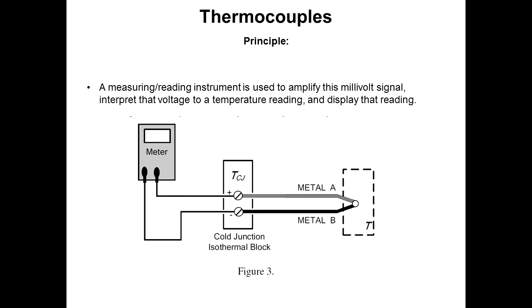So we have a measuring instrument here that amplifies this millivolt signal. The signal is very weak, so it needs to be amplified to be read by a meter. So I have a cold junction and a hot junction going to the meter. There's a thermistor on the cold junction measuring the temperature, and that gives me my ambient temperature, which is added back, or referenced to 0°C, and the difference is added back to the signal coming from the hot end of the thermocouple, and that's your temperature you're seeing.